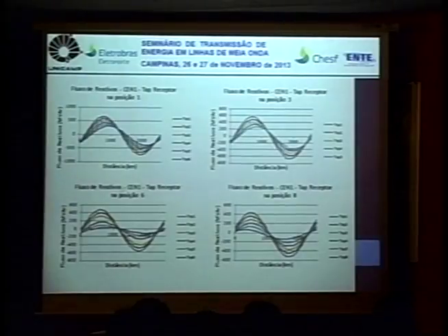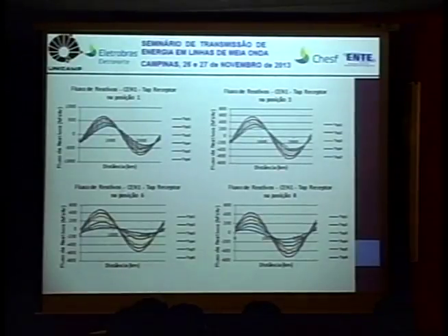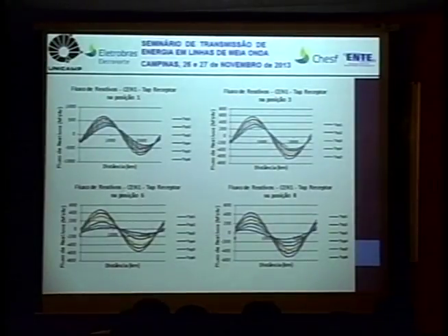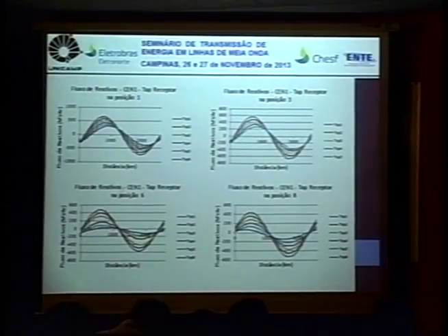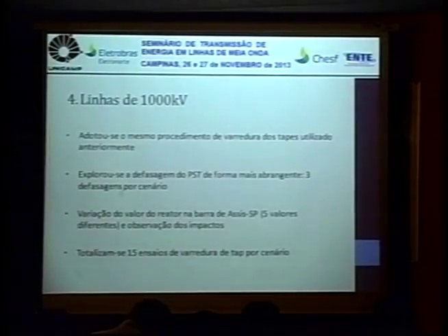If I do the same thing for all combinations, I can find one combination where I have very low reactive flows, low reactive injection in both terminals. So this is going to elevate my power factor closer to 1. By adjusting the tap close to the ideal one, this can improve the reactive power profile in the line, decreasing losses and improving the performance of the line.